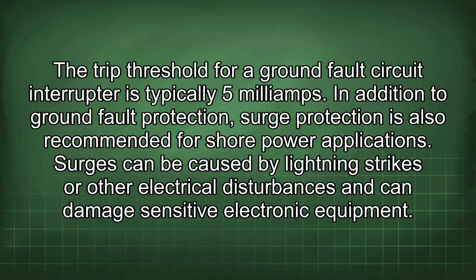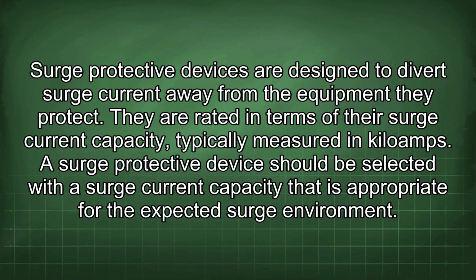In addition to ground fault protection, surge protection is also recommended for shore power applications. Surges can be caused by lightning strikes or other electrical disturbances and can damage sensitive electronic equipment. Surge protective devices are designed to divert surge current away from the equipment they protect. They are rated in terms of their surge current capacity, typically measured in kiloamps. A surge protective device should be selected with a surge current capacity that is appropriate for the expected surge environment.